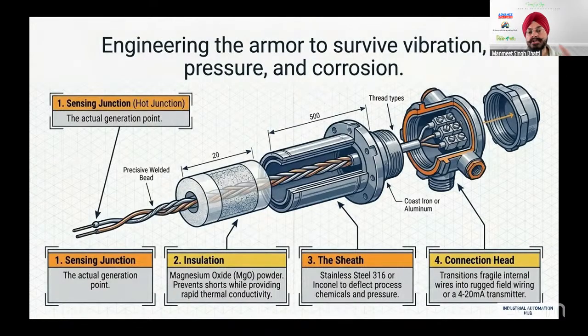But selection of a sensor is very, very important, in that you choose what kind of sheath is there. The sheath is very important because in the process, you are not measuring just temperature. Temperature is one parameter for measurement, but you might be having lots and lots of corrosive acids coming in. You might be having lots and lots of vibration coming in. So that sheath has to be designed based on the process conditions. That is the way it works. You must have seen this.